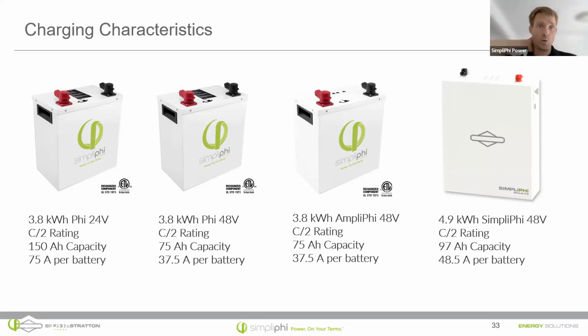So these are the charging characteristics of the batteries. It's important to note that our batteries are rated at C/2. If you're doing a charge from 0% up to 100%, what that means is the fastest you could charge these batteries safely would be 2 hours.